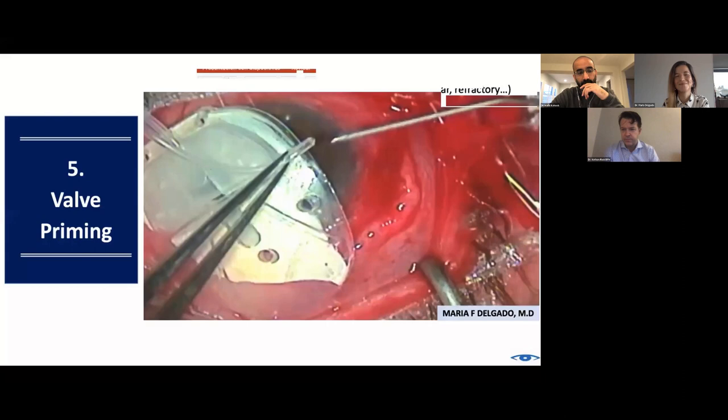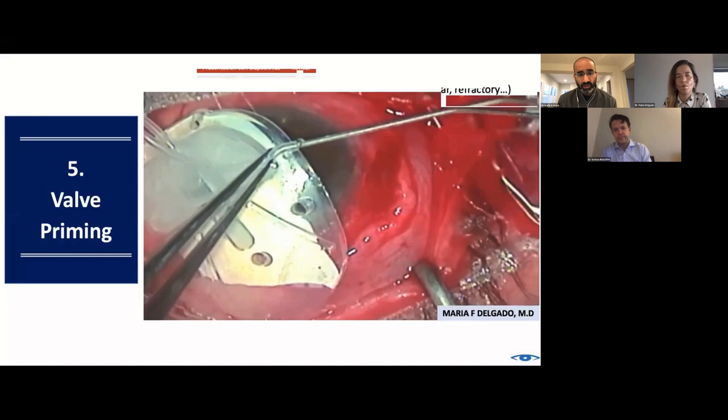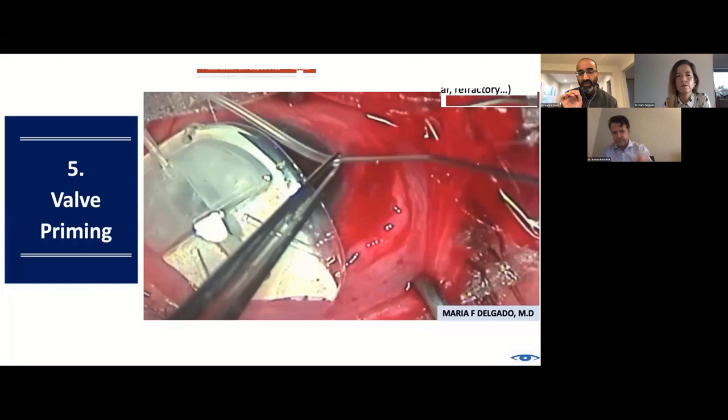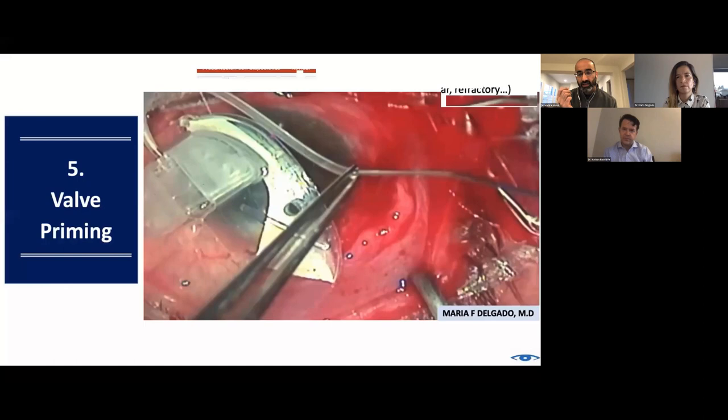This one, I think, and I'll ask Nate for his opinions on this. I think the priming part is a question that we get frequently. I do some work with New World, the New World medical device, the Ahmed valve, and every now and then calls will come in saying, hey, is it supposed to be a stream that's coming out? Is it supposed to be a trickle? There is no one-to-one relationship between the valve function and the stream that you're seeing coming out. It doesn't have to be a big stream. You don't have to be forceful.